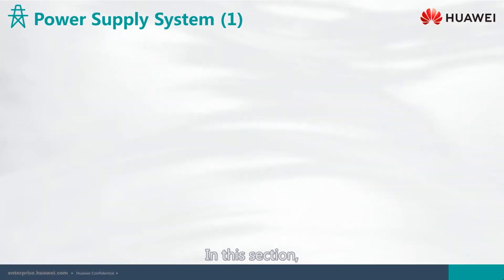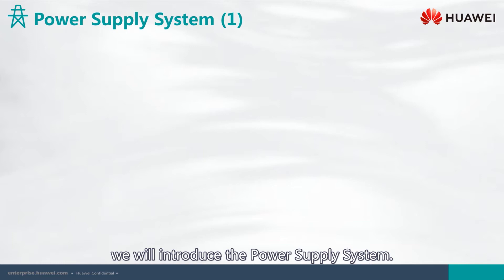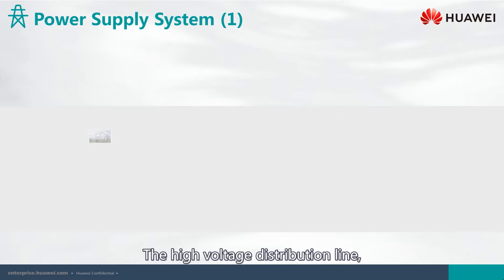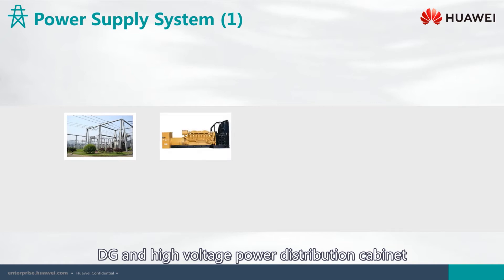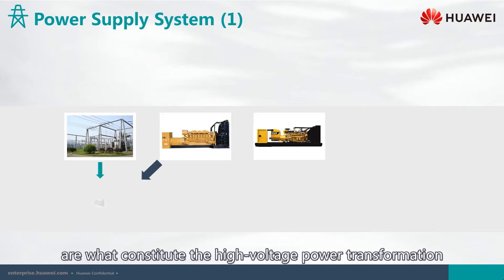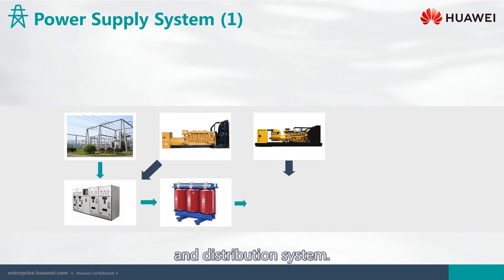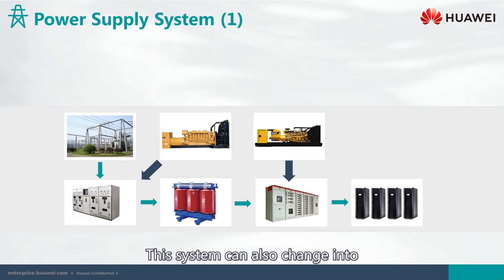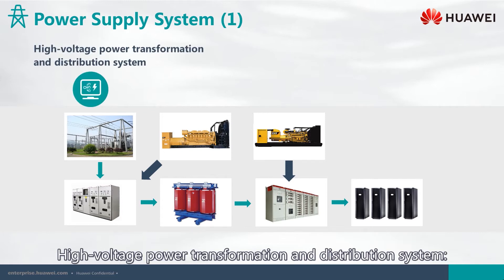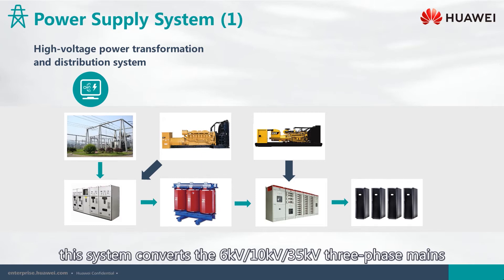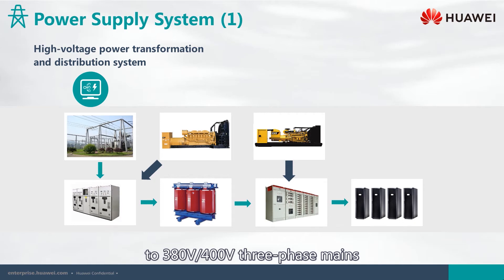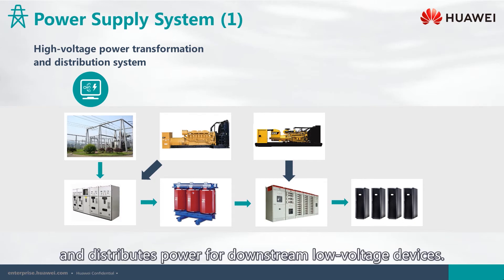In this section, we will introduce the power supply system. The high voltage distribution line, DG, and high voltage power distribution cabinet constitute the high voltage power transformation and distribution system. This system converts 6 kilovolt, 10 kilovolt, or 35 kilovolt three-phase mains to 380 volts or 400 volt three-phase mains and distributes power for downstream low voltage devices.